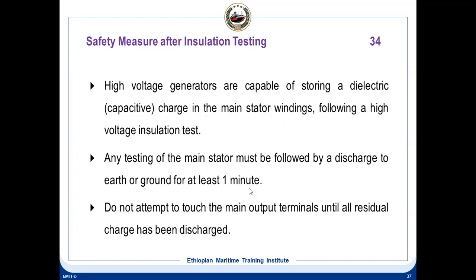It's very, very important. Most of the time we don't do this on board ship, but it can give a shock, especially in the case of high voltage equipment. You will never notice it. If you apply a 5000 volt Megger and don't discharge the residual charges, it can give a great shock. People ignore this, but you must discharge any stored charges.